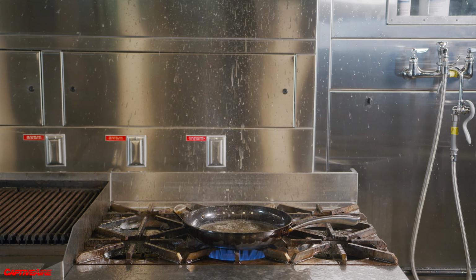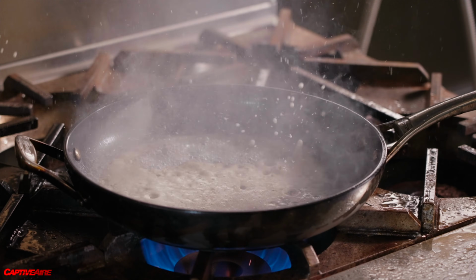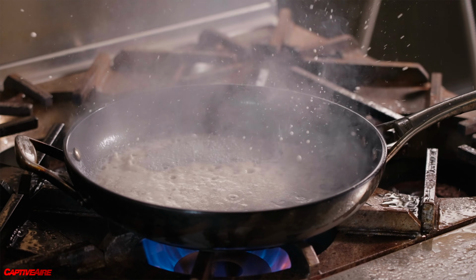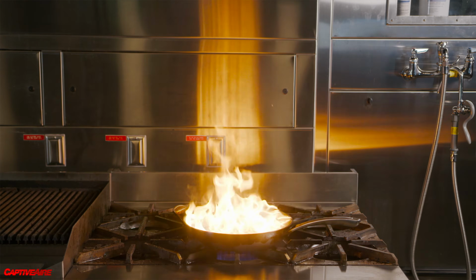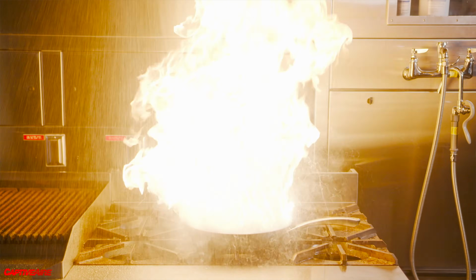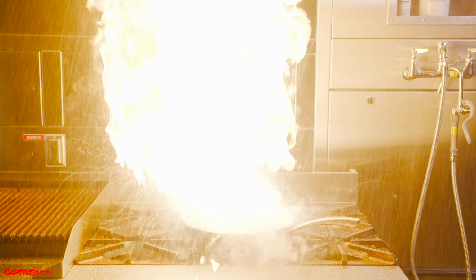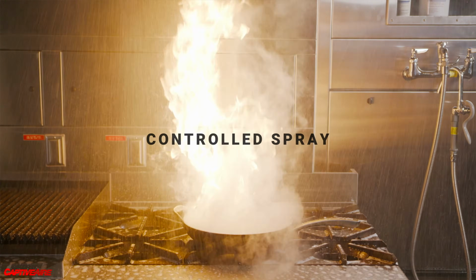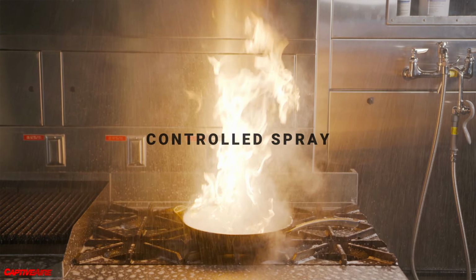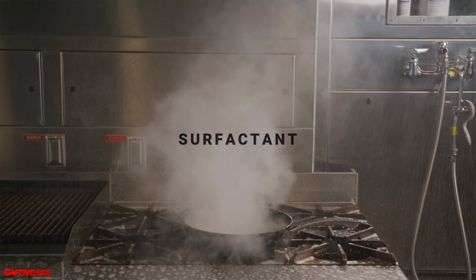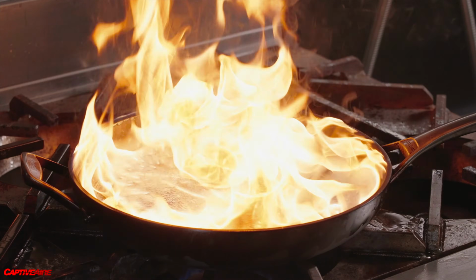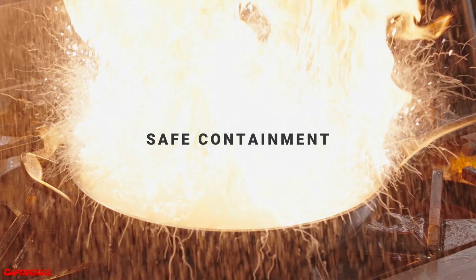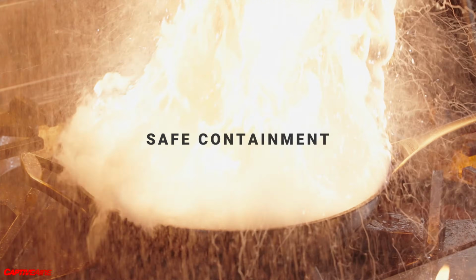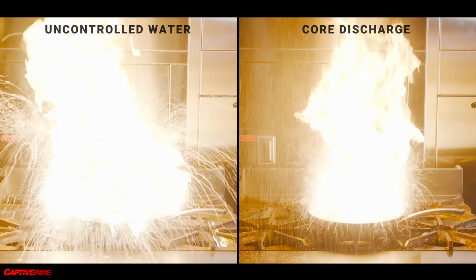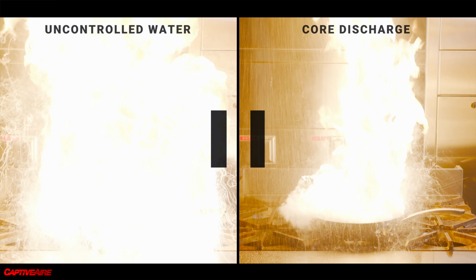Even after the fire is put out, this mix just keeps splattering everywhere. But look at the difference with Core. With a controlled spray pattern resulting in small droplets, and the addition of surfactant to help mix the water with the oil, the fire is contained safely. Let's see the two side by side - the difference is pretty clear.